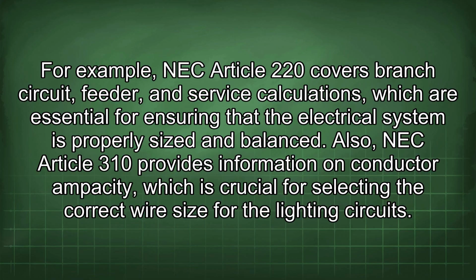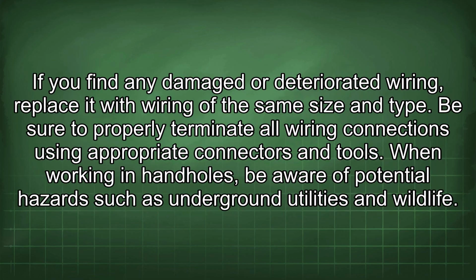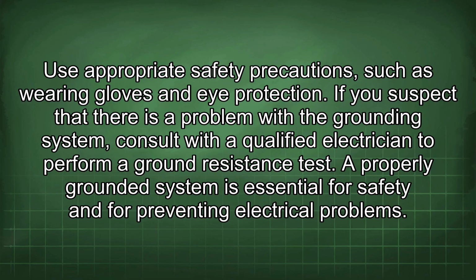Also, NEC Article 310 provides information on conductor ampacity, which is crucial for selecting the correct wire size for the lighting circuits. If you find any damaged or deteriorated wiring, replace it with wiring of the same size and type. Be sure to properly terminate all wiring connections using appropriate connectors and tools. When working in hand holes, be aware of potential hazards such as underground utilities and wildlife. Use appropriate safety precautions such as wearing gloves and eye protection.